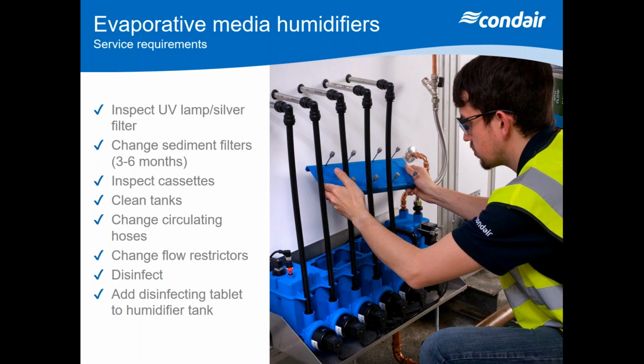You can also have silver filters, which will dose silver into the system, and silver will just act as an inhibitor. It won't kill at the same rate as a UV system will do, but it will actually keep that tank in check. The most important thing to consider with these systems is water movement, making sure the water is being moved through the system, purging the line before the system, and making sure the unit dilutes on a regular basis. Also, what we recommend is you take the cassettes out, because obviously you can see the face area at the front might be scaled, but if you're taking them out, you're going to have an appreciation for how heavy they're getting to give you an understanding when you will replace those cassettes.